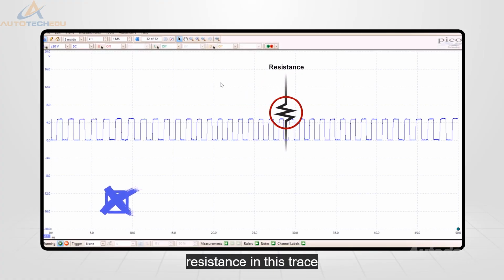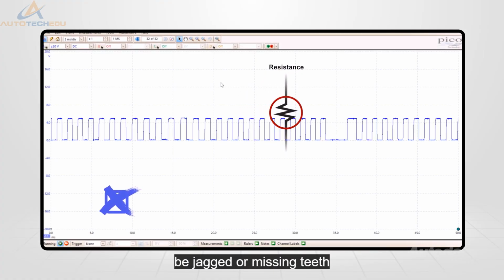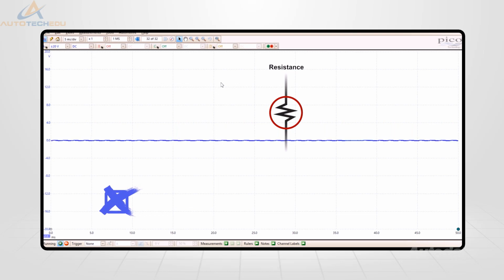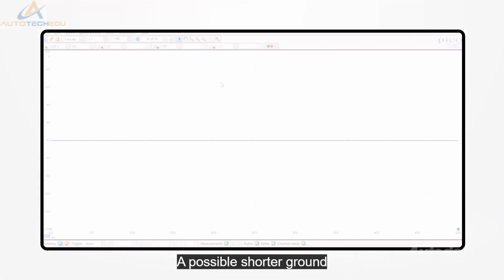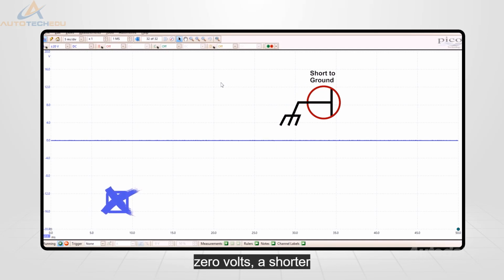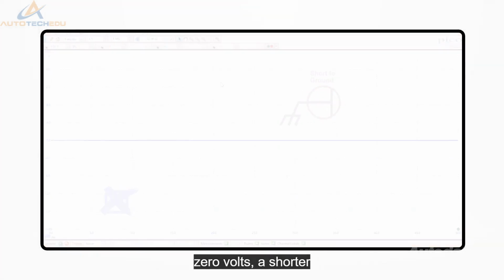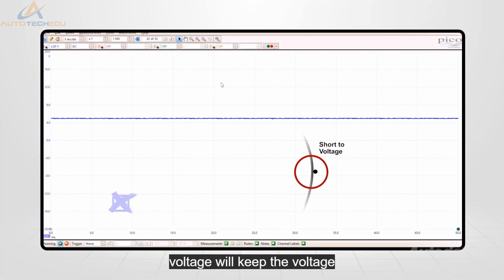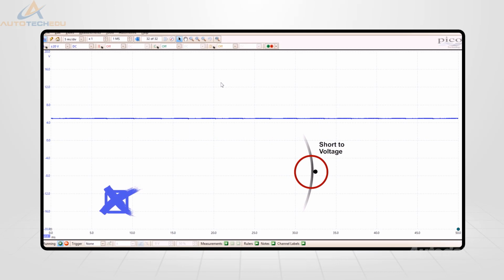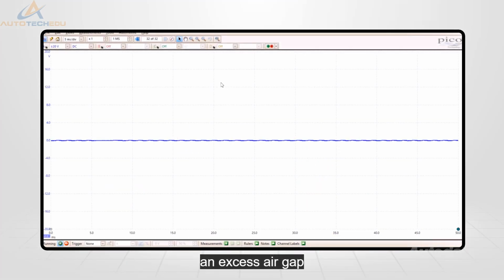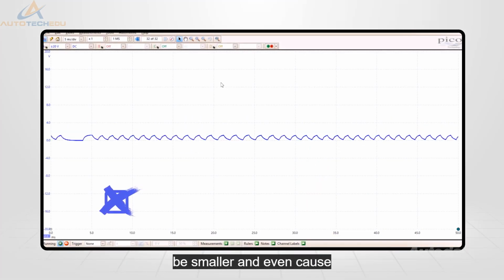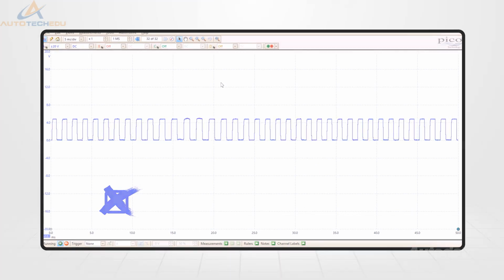Resistance in this trace will cause the reading to be jagged or missing teeth. A possible short to ground in this circuit will display 0 volts. A short to voltage will keep the voltage at a constant high. An excess air gap can cause the peaks to be smaller and even cause there to be no signal.